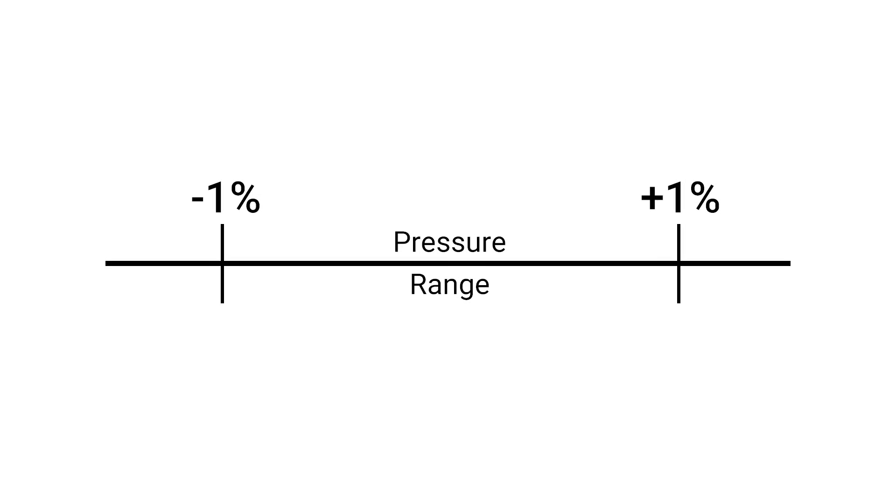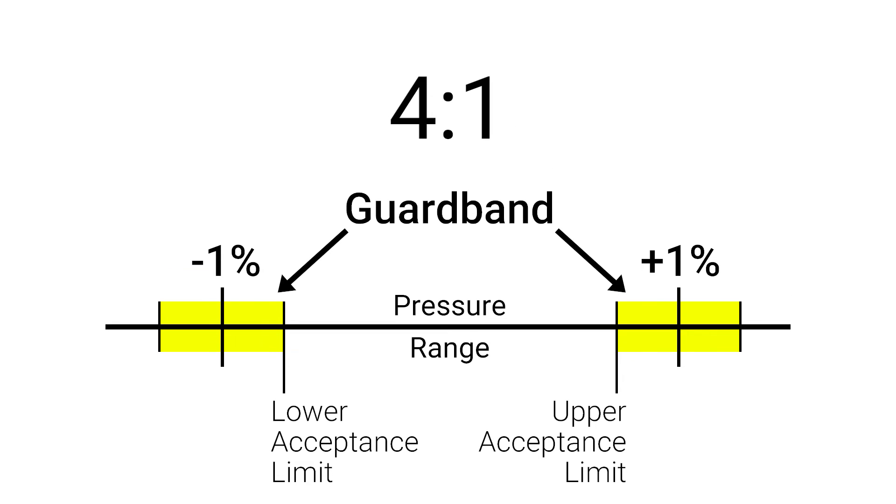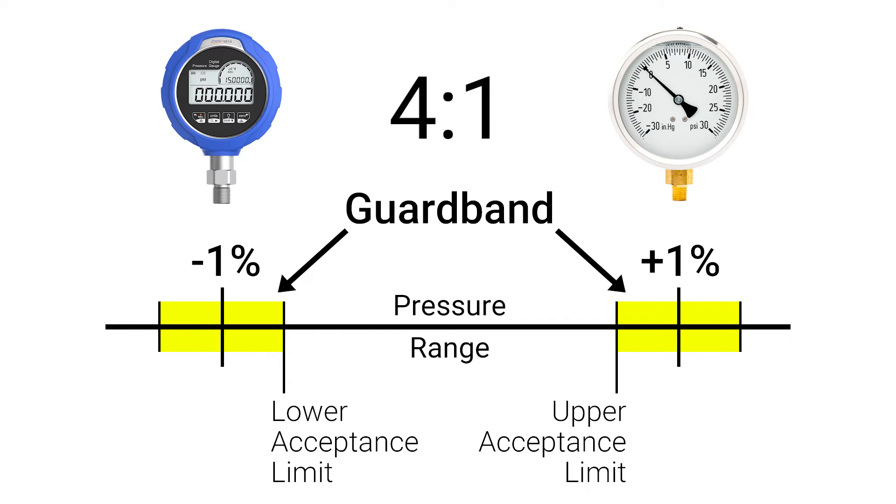Within the specified accuracy range are upper and lower acceptance limits for pass or fail decisions. The difference in these limits to their respective specifications is called the guard band, which may change depending on the accuracy ratio between the test device and the reference standard.